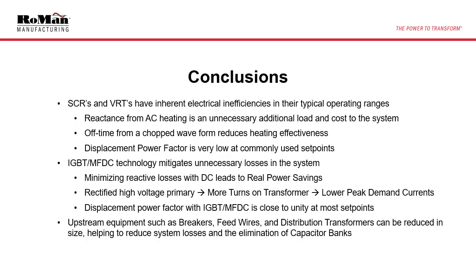In conclusion, SCRs and VRTs have inherent electrical inefficiencies in their typical operating ranges. The reactance from AC heating is an unnecessary additional load and cost to the system. The off time from a chopped sine wave reduces heating effectiveness, and displacement power factor is very low at commonly used set points. With IGBT MFDC technology, however, these unnecessary losses in the system are mitigated by minimizing reactive losses. A rectified high voltage primary means more turns per transformer, which leads to lower peak demand. And displacement power factor with IGBT MFDC is close to unity at most set points.